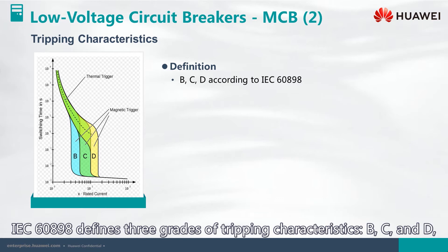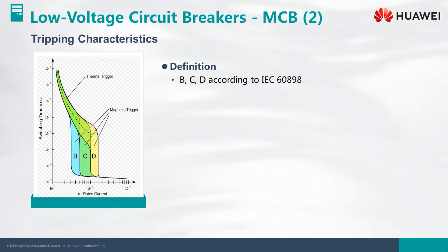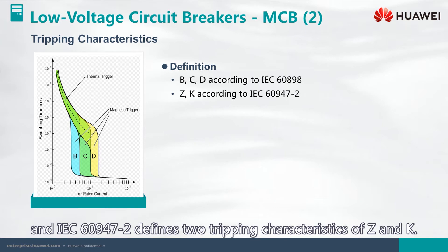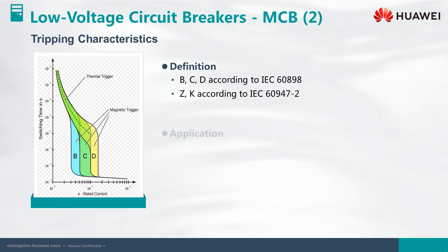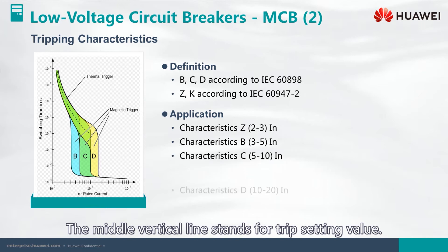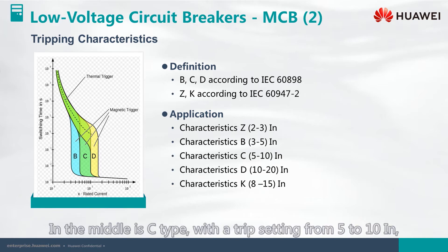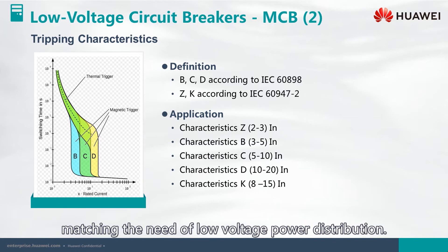IEC 60898 defines three grades of tripping characteristics: B, C, and D. IEC 60947-2 defines two tripping characteristics: Z and K. The middle vertical line on the curve stands for the trip setting value. C type is in the middle, with a trip setting from 5 to 10 times rated current, matching the needs of low voltage power distribution.